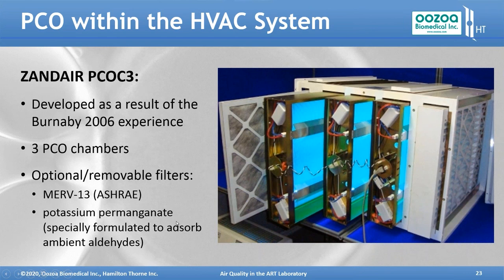There are some optional or removable filters you can put here as well. It's a typical MERV 13 filter. It's a standard. If you look up these things under ASHRAE, that's the American Society for Heating, Refrigeration and Air Conditioning Engineers. ASHRAE will take you straight to their website via Google. MERV 13 is a filter that's approaching HEPA levels, but they also include potassium permanganate, which will adsorb any ambient aldehydes as well.